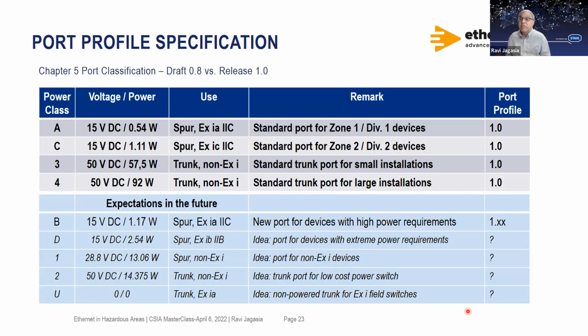What are the profiles already available in release 1? You have the profile for the SPURs, for zone 1, div 1, for zone 2, div 2. You can do it in zone 1, div 1, because the power requirements would be less, you would be only getting 540 milliwatts. But for the zone 2, div 2 devices, where you can run more energy into those hazardous areas, you could do 1.11 watts. And then, of course, you have the non-Ex i trunk. The non-Ex i trunk is the Ex e trunk in the standards if you compare it with IEC or ATEX. But under the NEC 500, it will be a non-incendive trunk.